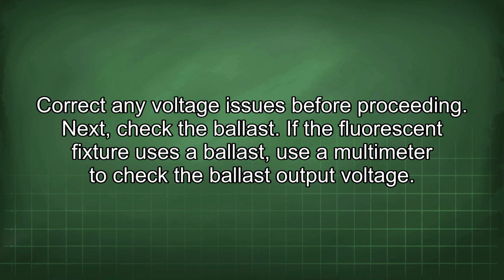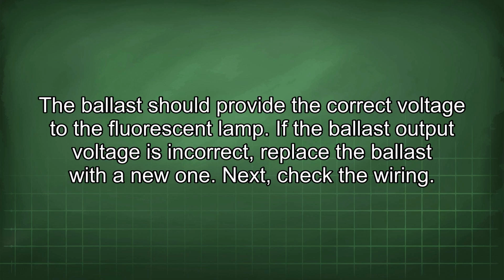Next, check the ballast. If the fluorescent fixture uses a ballast, use a multimeter to check the ballast output voltage. The ballast should provide the correct voltage to the fluorescent lamp. If the ballast output voltage is incorrect, replace the ballast with a new one.